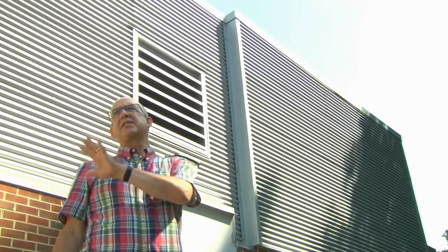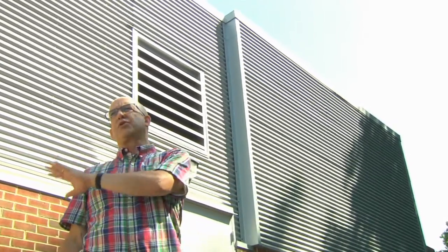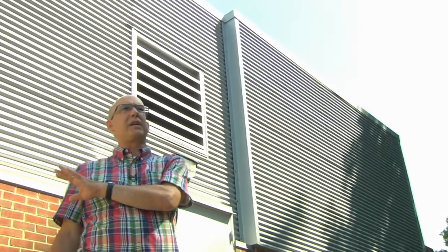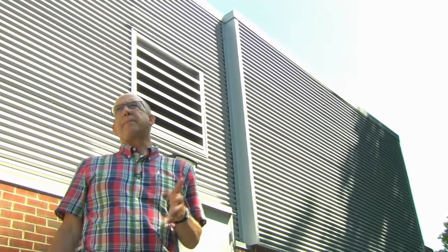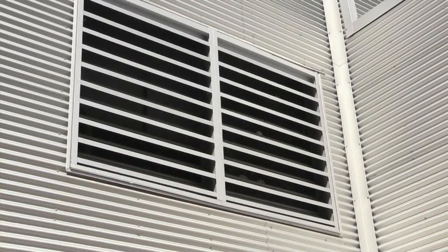You've got several spaces like this on campus. I'm sure you have other spaces like this in this building where you might be able to raise the set point perhaps. If we look right above our heads over here, we see an intake louver. You can see some leaves in there, it's not bad. Those are the types of intake louvers we want to look at. Make sure they're not filling up with grass clippings or leaves if they're starting to become a restriction.